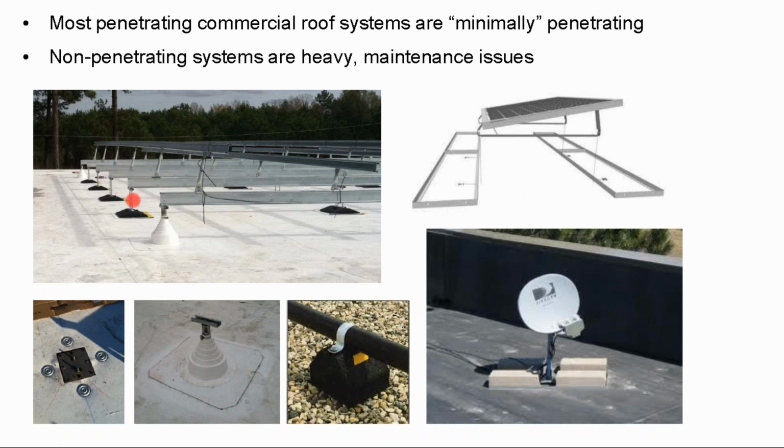On this elevated racking structure, the way that we got around the dead weight issue, because on this particular warehouse, the engineer came back and said, it cannot support 10 pounds a square foot of dead weight. It needs to be less than that.